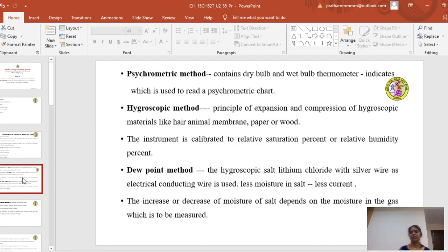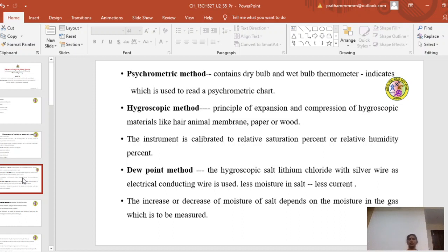The psychrometer is used to measure the moisture of a drying medium. You record the dry bulb temperature and the wet bulb temperature. Using those two temperatures in the psychrometric chart, we measure the relative humidity, specific humidity, or percent humidity by the psychrometric method.